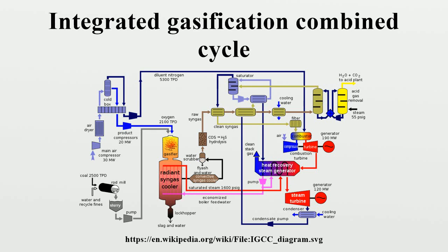Installations: the DOE Clean Coal Demonstration Project helped construct 3 IGCC plants: Wabash River Power Station in West Terre Haute, Indiana, Polk Power Station in Tampa, Florida, and Pinon Pine in Reno, Nevada. In the Reno demonstration project, researchers found that then-current IGCC technology would not work more than 300 feet above sea level. The DOE report in reference 3, however, makes no mention of any altitude effect, and most of the problems were associated with the solid waste extraction system. The Wabash River and Polk power stations are currently operating, following resolution of demonstration startup problems, but the Pinon Pine project encountered significant problems and was abandoned.